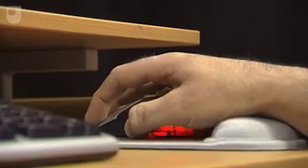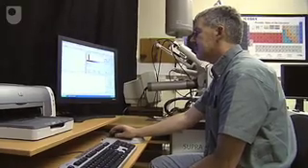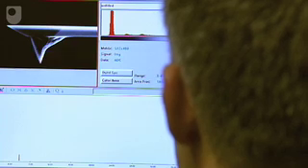For analysis purposes we capture the image, but instead of scanning the beam back and forth across the specimen, we can position it in one particular spot of interest and derive an analysis from that point. By increasing the beam energy we can stimulate the specimen to emit X-rays, and these X-rays are characteristic of the elements that are present in the specimen.